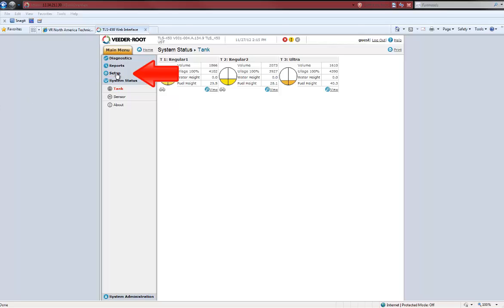From the main menu column, select Setup. You will notice these selections are in alphabetical order. If you are using Web-Enable, there is a logical order to program a console. You should start with date and time, which can be done through the GUI. Headers should be next, followed by Device, Tanks, Product, Tank Charts, Pumps and Lines, Inventory, Delivery, BIR, and finally Automatic Events. If you follow this order, you will cut down the number of setup data alarms and possible programming issues.